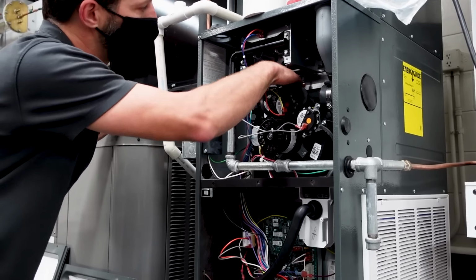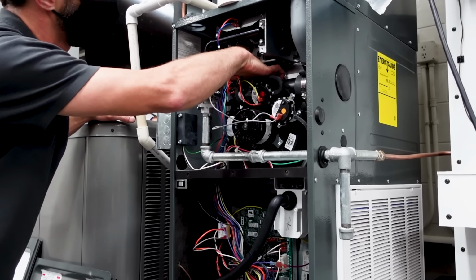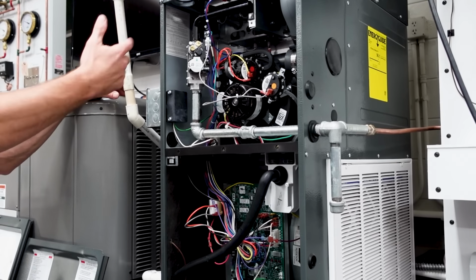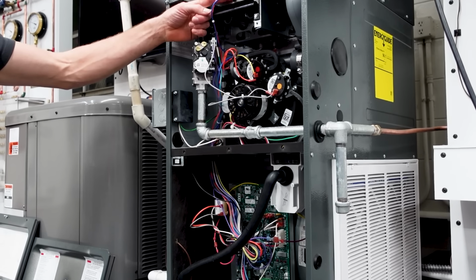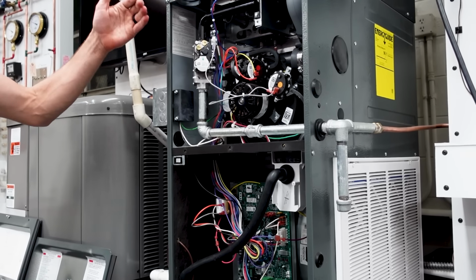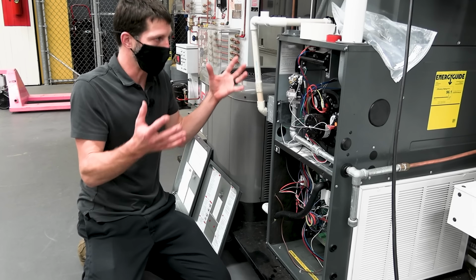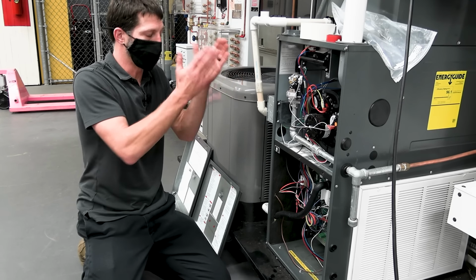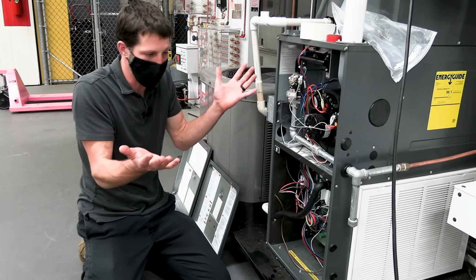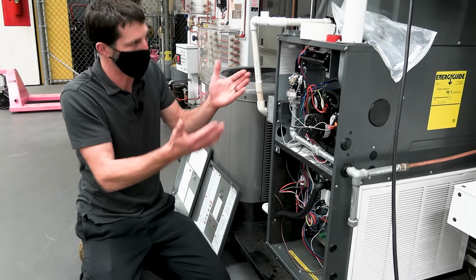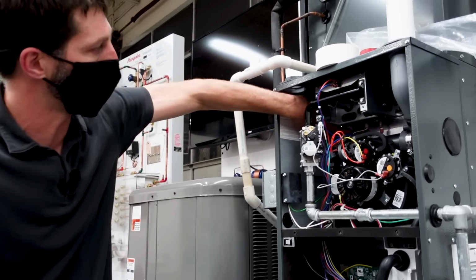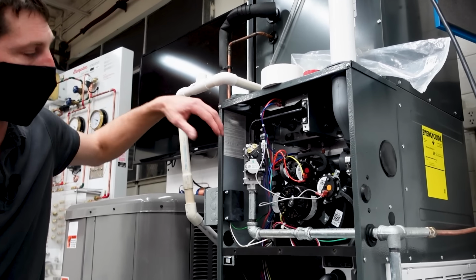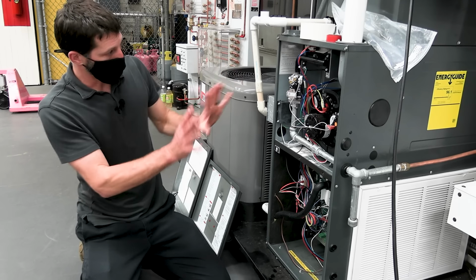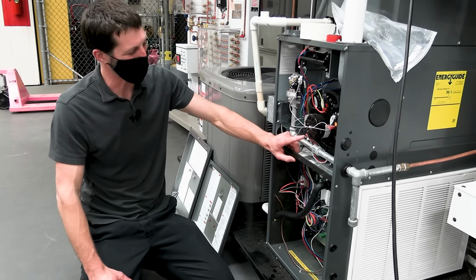And you actually have a little scan on this particular one where you can take your phone and scan it. But a lot of them have their temperature limits on them where they open up at, and then they close back down again at whatever it is minus a certain amount, 20 degrees or something like that. Not on this one, but on the automatic ones, they're just an automatic bimetal disc. All right, getting back to all of this because I'm getting on a bunch of tangents.